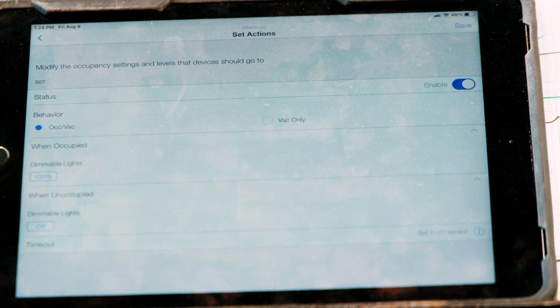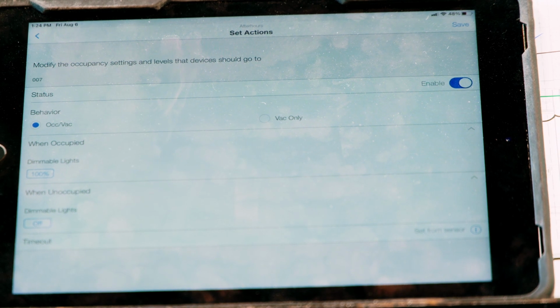But you also have Pico switches in all of the different rooms, right? So what can happen is, like in a bathroom, for example, there are Pico switches in there. Somebody walks in, the lights turn on, the 15 minutes starts, right? The person leaves the bathroom and turns the lights off with the Pico, while the occupancy sensor is still in its timer for the 15 minutes. If a person walks in before the 15 minutes are over, the lights will not turn on with the occupancy sensor because it's still in its occupied state.